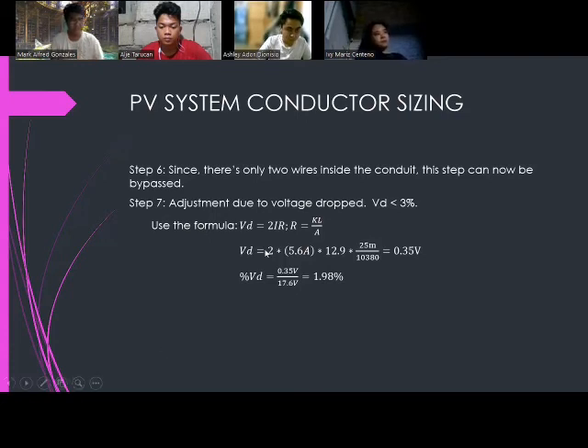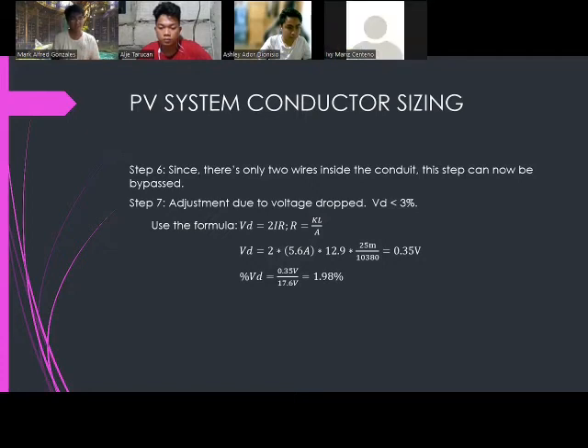So as you can see, 2 multiplied by I, yung I natin is 5.6 yung kanina. K, which is a constant 12.9. Yung length na ginamit natin is 25 meters, for example, na di namin calculate. Ayan, mahaba ang bubong. At yung A, which is 10,380 mils, which will give us a 0.35 volts na voltage drop. To calculate the percentage, we divide that simply by the 17.6 volts na na-output ng solar panels, which will give us 1.98% of voltage drop, which is well below the 3% requirement.